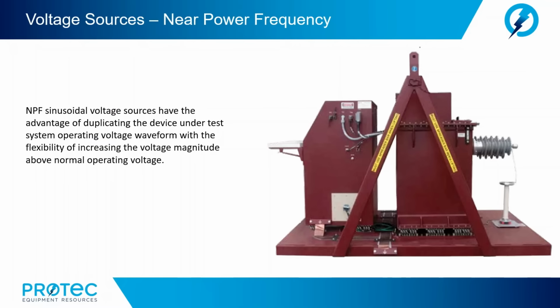Okay, now let's take a closer look at alternates to the power frequency test equipment. As we already established earlier in this webinar, the capacitance of a specimen could cause us issues in field testing at power frequency. Because of the capacitive reactance, as we saw in our examples, the size, weight, and cost of a power source capable of performing the testing in the field might be very large, cumbersome, and expensive. So let's explore the possibility of near power frequency test equipment. Near power frequency sinusoidal voltage sources have the advantage of duplicating the device under test system's operating voltage waveform with the flexibility of increasing the voltage magnitude above normal operating voltage.